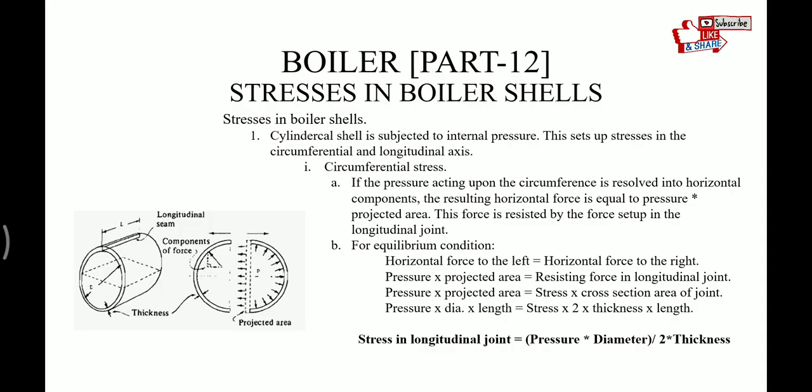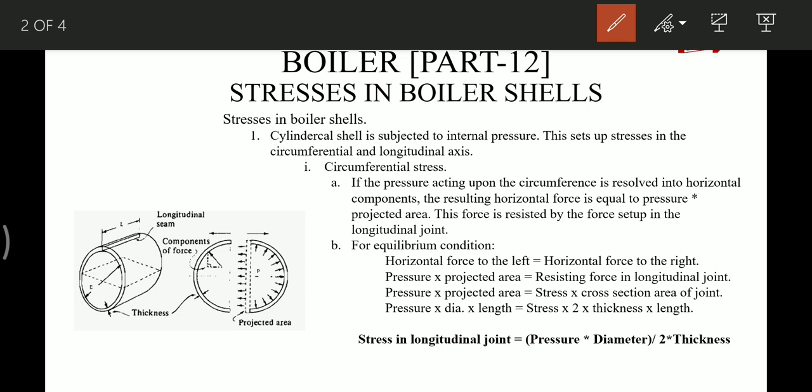Stresses in the boiler shell. The cylindrical shell is subjected to internal pressure, which sets up stresses in the circumferential and longitudinal axis. For the circumferential stresses: if the pressure acting upon the circumference is resolved into horizontal components, the resulting horizontal force is equal to the pressure into the projected area. This force is resisted by the force set up in the longitudinal joints. For equilibrium, horizontal force to the left equals horizontal force to the right — that is, pressure into projected area equals the resisting force in the longitudinal joint.